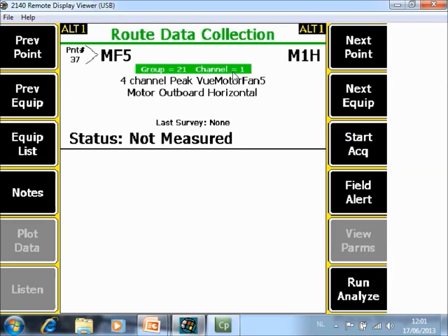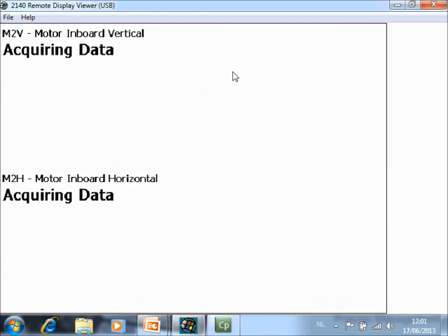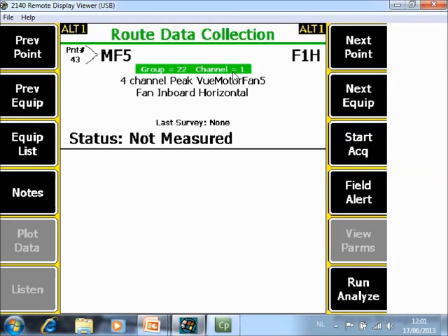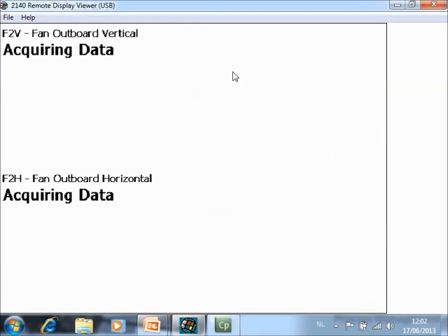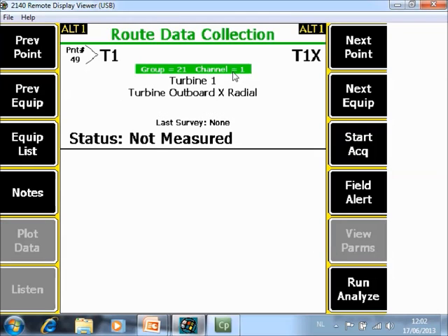In the next machine I also added the PeakVue, so now in every plane I have six points. On the analyzer you see four points collected first, and then automatically the two remaining points are collected in sequence. Six measurements are done and it jumps immediately to the next component. The machine is done.